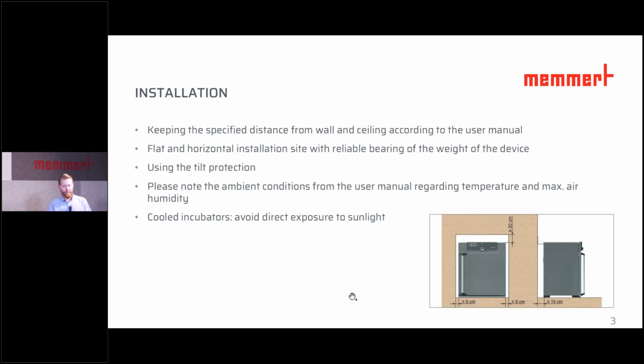So starting with the installation, when setting up a unit in a laboratory, it's important to maintain the minimum distances from walls and to ensure sufficient ventilation as specified by the manufacturer. Every unit, regardless of its operation temperature, emits heat energy into the environment. If units are placed too close to each other or to the wall, a rising ambient temperature can affect the temperature control within the unit.